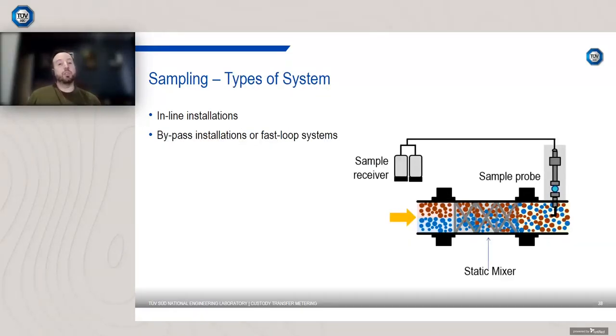And in terms of types of sampling system, you can get inline installations that take the sample directly from the main flow stream, or you can get bypass or fast loop systems that will quickly bypass the flow and then take a sample in that way. There are pros and cons to each of these, and obviously sampling as a topic has more detail than I can go into in the short four slides that I've got here.